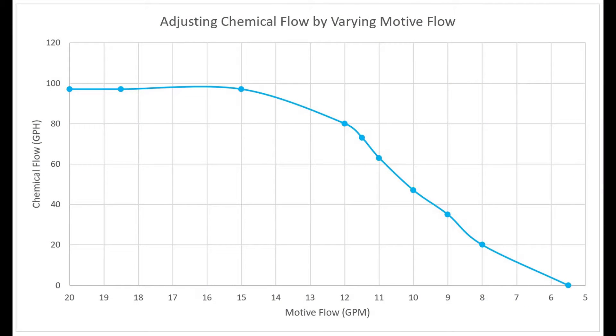Here's a graph showing the motive flow compared to the chemical flow. The motive flow is on the horizontal axis and the chemical flow is on the vertical axis. Our first point, with a motive flow of 20 gallons per minute, equaled 97 gallons per hour. As we reduced the motive flow, the chemical flow rate did not change at first, but then we hit a point where the chemical flow started reacting sharply — and this is what makes it difficult to adjust chemical flow with the motive flow rate.